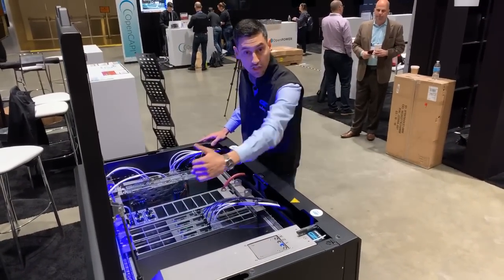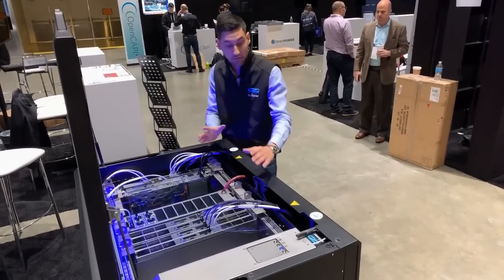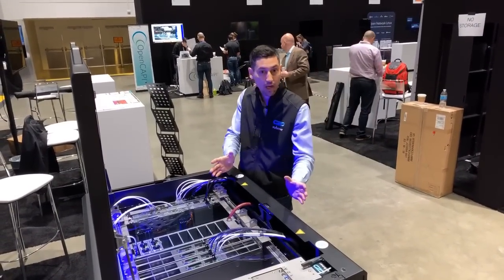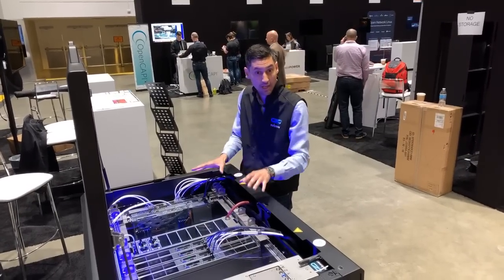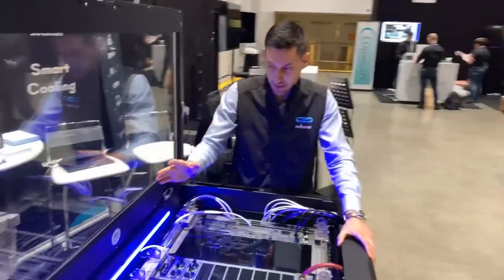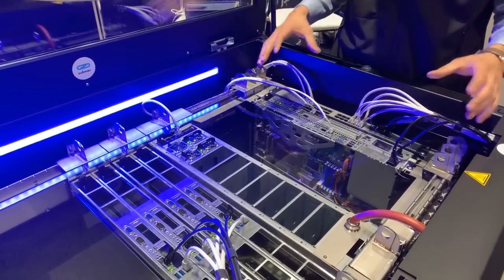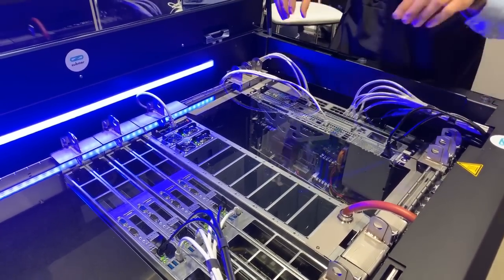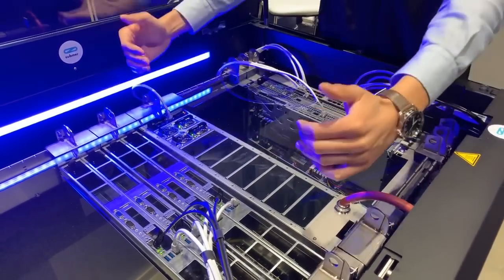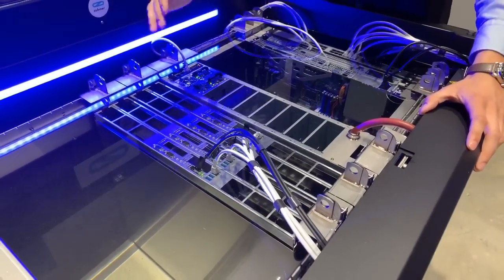We have the 21-inch rack, but with adaptability for a 19-inch regular rack, so we can be flexible. Our co-location customers will love it, because they can have an OCP rack, or a 19-inch rack, or even both of them in the same place. At the end, we have a 19-inch regular rack with our adapter to place any kind of computing here. From here, we have the open-compute power supply, and we can place 21-inch open-compute hardware.